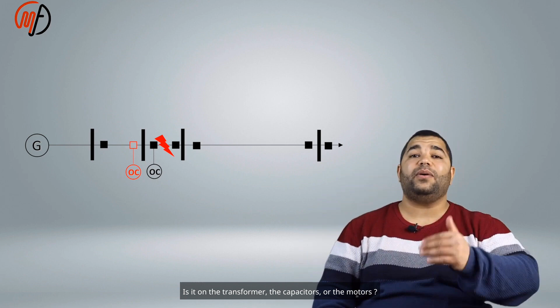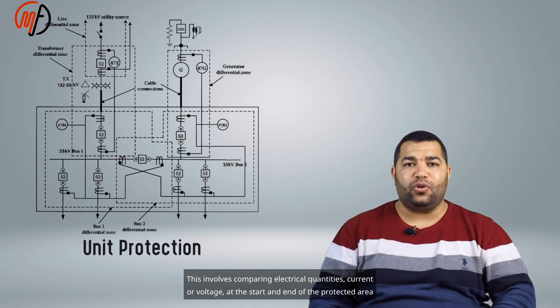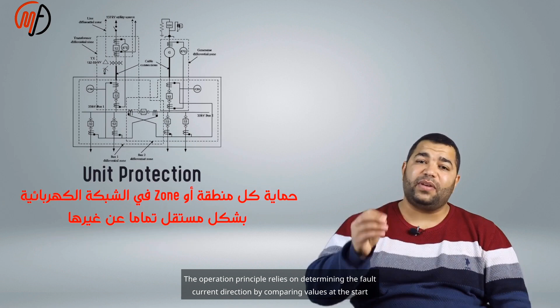These issues were the reason for the search for a different protection method, leading to unit protection, protecting a specific network area independently. This involves comparing electrical quantities, current or voltage, at the start and end of the protected area. The operation principle relies on determining the fault current direction by comparing values at the start and end of each zone. Any protection comparing electrical quantities, current or voltage, between the beginning and end of the protected area is referred to as such.